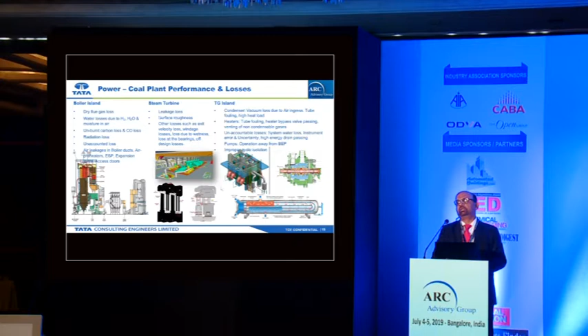Over the last couple of years, we've developed a boiler performance tool. Boiler has traditionally been an OEM IP, and the operating people have had to depend on the OEM. What this does is predict thermal profiling, including metal temperature, across the entire boiler, right from the furnace to the reheater to the superheater to the economizer.